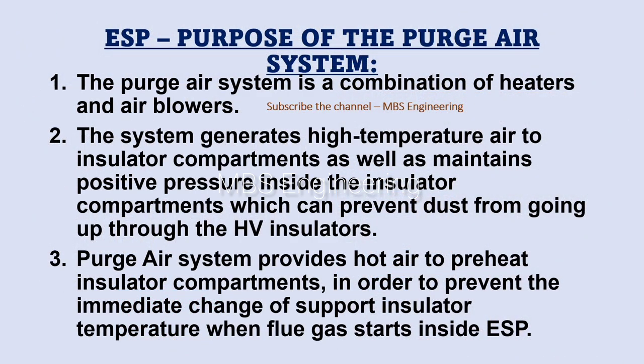Next, we are going to discuss the purpose or function of the purge air system in the ESP. Point one: the purge air system is a combination of heaters and air blowers. Point two: the system generates high temperature air to insulator compartments, as well as maintains positive pressure inside the insulator compartments, which can prevent dust from going up through the HV insulators.